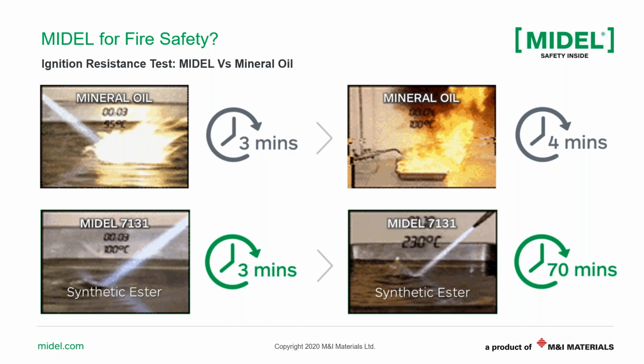Now, to give you more sense of the fire aspect, these are 4 images you can see here of a test we conducted by filling a pan with the liquid. So the top 2 pictures are for mineral oil, the bottom 2 pictures are with MIDEL 7131 synthetic ester. And the idea here with the pan, we inserted a thermocouple to measure the average liquid temperature, filled the pan with the liquid, and then exposed the pan surface to an external flame, an oxyacetylene torch. Now, typically the flame temperature is 3000 degrees.